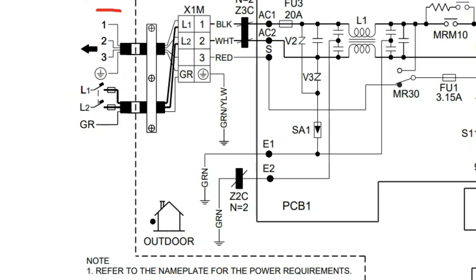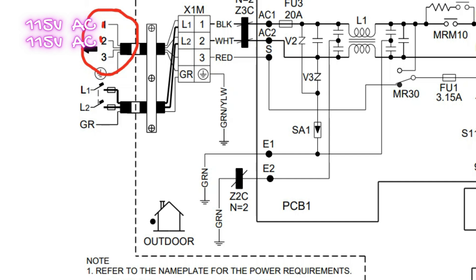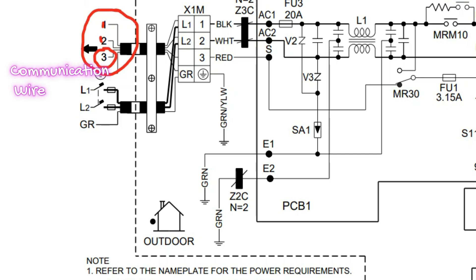Over here we have our power going to our indoor unit on terminals 1 and 2. That is 115 volts AC on each one of those to deliver 230 to the indoor header. Terminal number 3 is our communication wire.